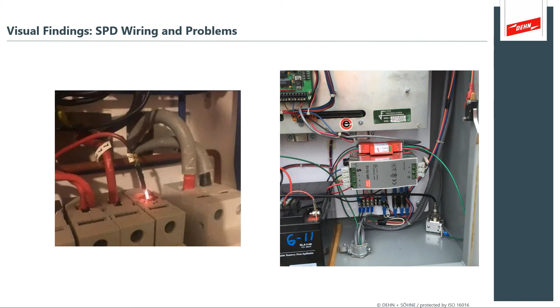What are we looking for? Visual findings. This is what we're looking for. We're looking for the application of surge devices. We're looking for the position near the point of use, short connection wires, avoiding tight bend radius, using the largest, heaviest gauge wire practical, direct connections to the earthing bar. These are the things we're looking for. So when you see it, you recognize it.